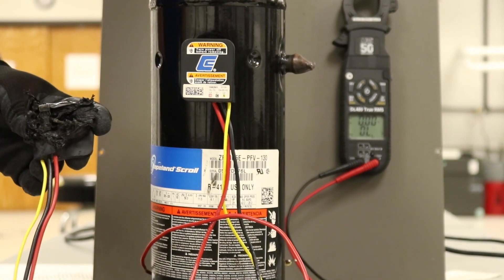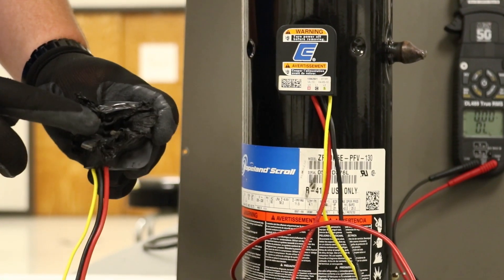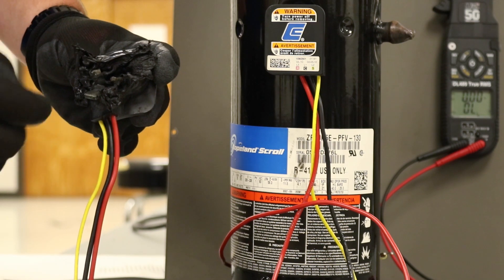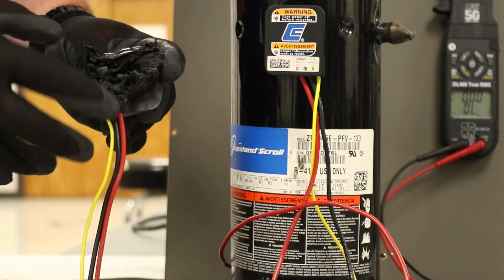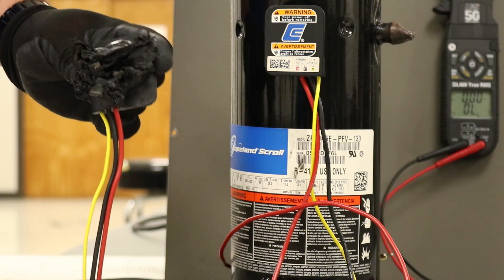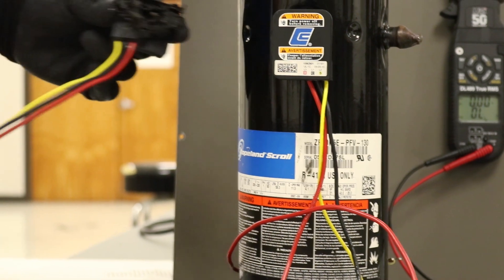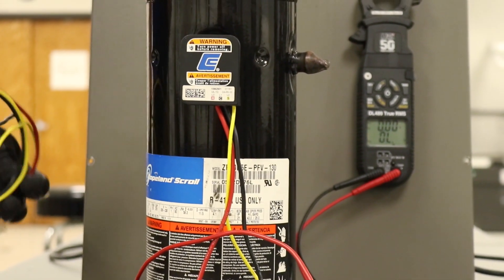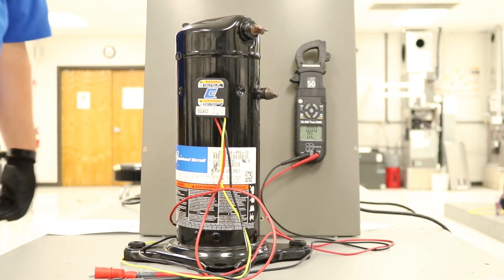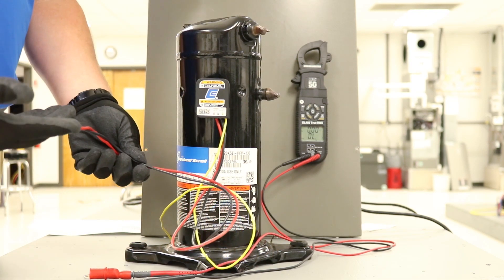As you can see on this plug, the connectors go straight to those terminals. One of the terminals on this compressor is still connected to this plug — it was obviously hot enough that the rubber and plastic composite was melting, and it's flared out because all of the refrigerant in the system immediately left. You want to make sure to avoid this if you can.